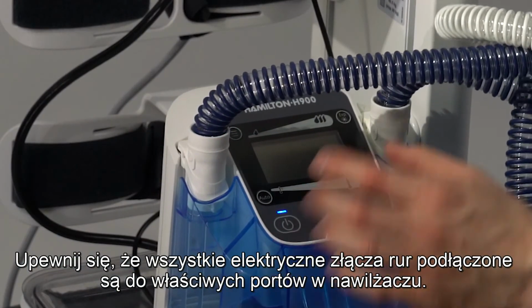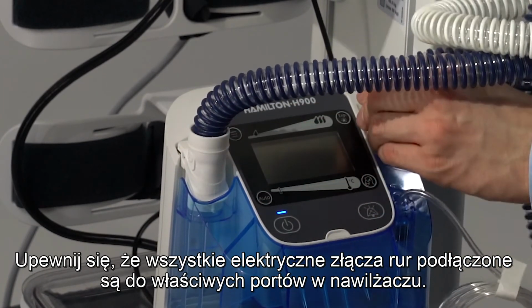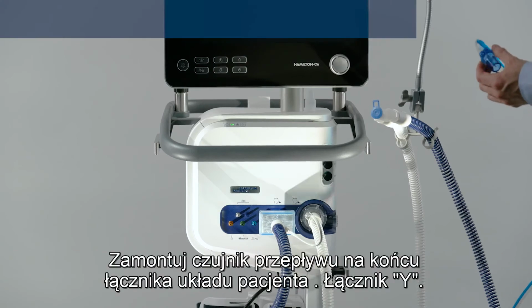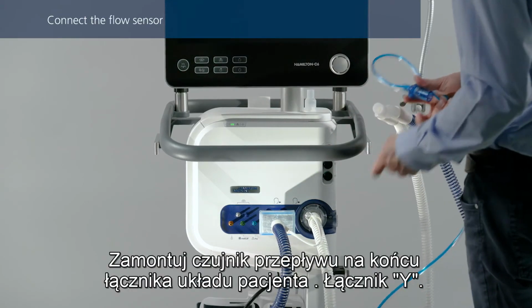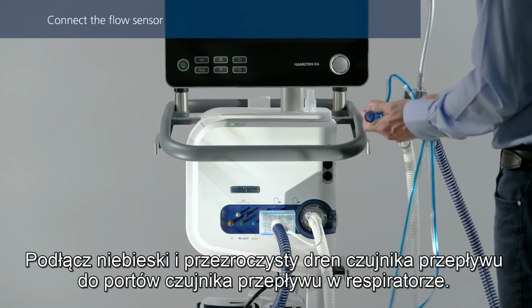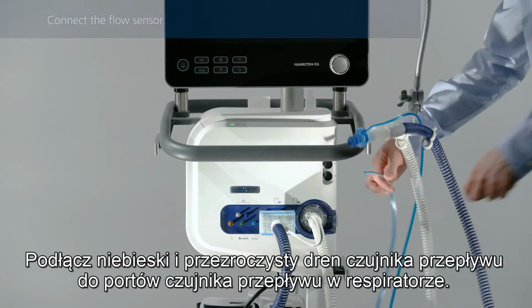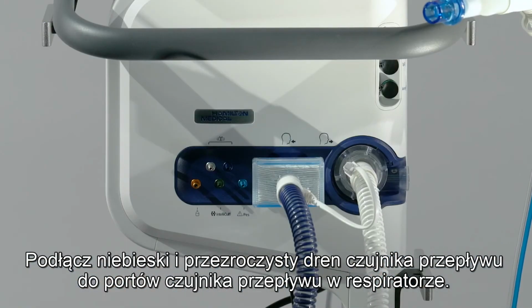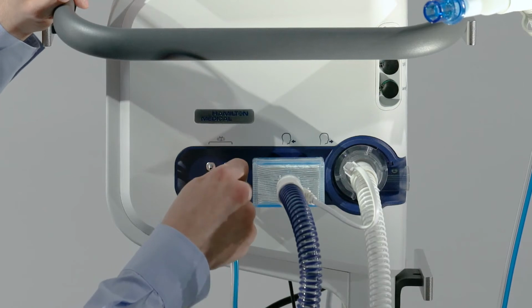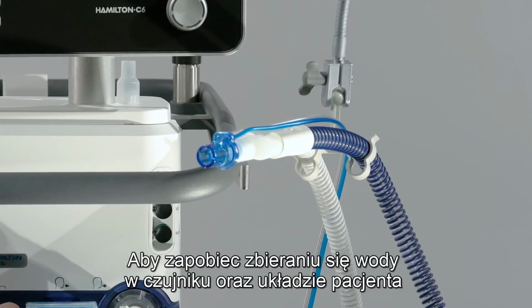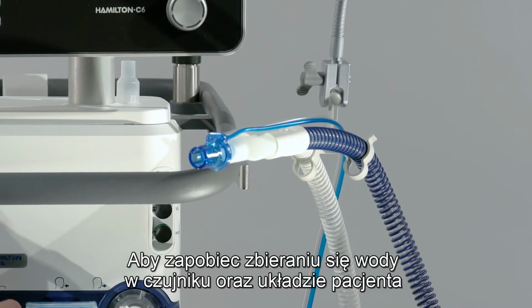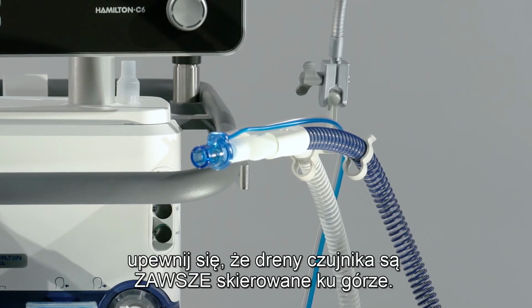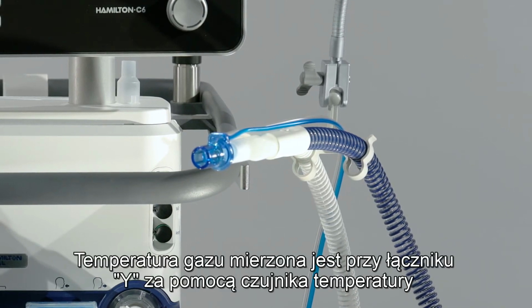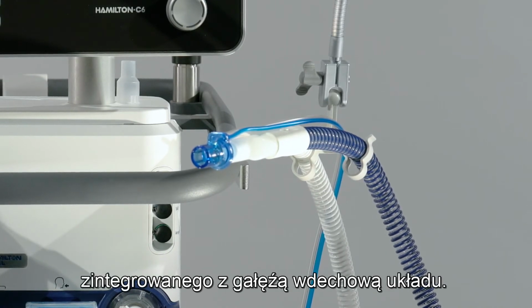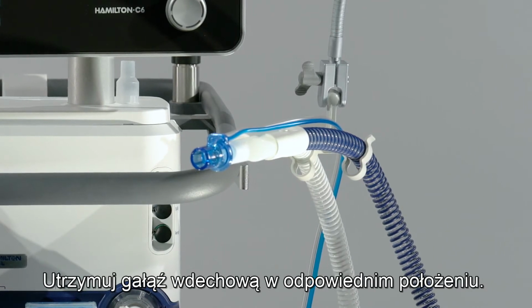Make sure that all electrical contacts on the breathing circuit match the connecting element on the humidifier. Insert a flow sensor into the breathing circuit in front of the patient connection, that is, the Y-piece. Attach the blue and clear tubes to the flow sensor connection ports on the ventilator. To prevent water accumulating in the flow sensor and tubing, position the flow sensor tubing on top of the flow sensor. The gas temperature is measured at the Y-piece by means of the temperature probe integrated in the inspiratory limb. Keep the inspiratory limb positioned correctly.